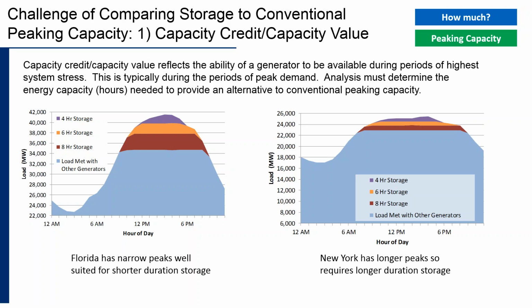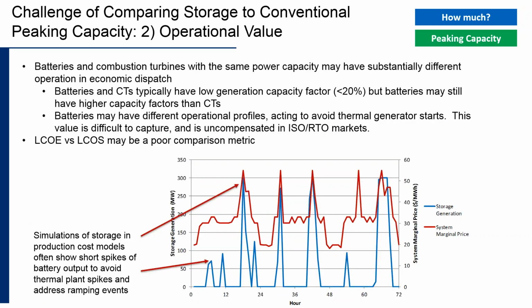Alternatively, regions like New York, which are also summer peaking but have longer duration peaks, may have less ability to use 4-hour storage. You may need 6 or even 8-hour storage to provide a significant amount of peaking capacity. So analyzing the ability of storage in each specific location to see whether it can provide that peaking capacity is a key part of comparing peaking storage with peaking thermal capacity.